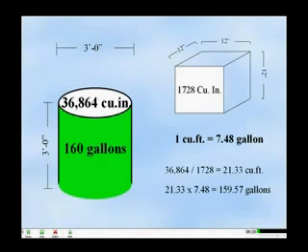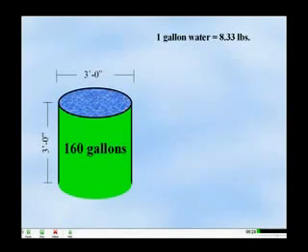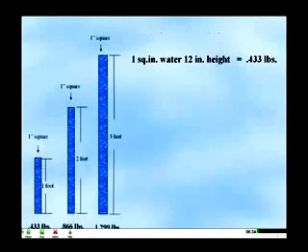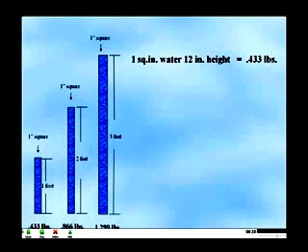Water weighs 8.33 pounds per gallon. Water also exerts 0.433 pounds per square inch per foot in height. Add another foot on top of the first, and the PSI increases by 0.433 pounds per square inch. A pipe that is 100 feet in height will have a PSI reading of 43.3 PSI at the bottom of the pipe. Every foot of height also added onto it will increase the weight by the same amount. So if you have a 10-foot stack pipe filled with water, it will exert 4.33 pounds PSI at the base of the pipe. Many times, a plumbing inspector requires the soil system to be tested by having all openings tightly closed and a 10-foot vertical pipe to be filled with water for a minimum of 15 minutes. This subjects the system to a 4 to 5 PSI pressure throughout to verify a leak-proof system.